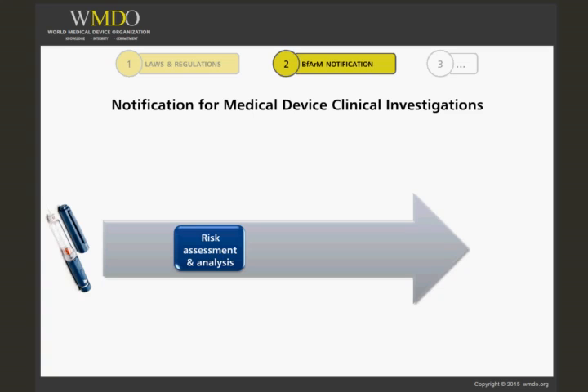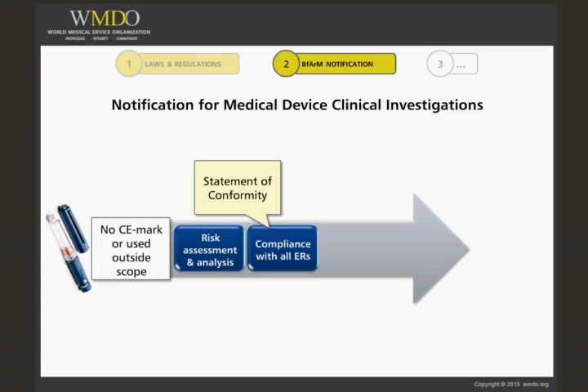Further to be taken into account is that for clinical investigations with non-CE marked devices or devices used outside CE mark scope, the manufacturer must ensure the device complies with all essential requirements as outlined in the Annex 1 of the applicable Medical Device Directive. A statement of conformity must be issued by the manufacturer or sponsor that confirms that the device complies with all essential requirements, except those still to be proven by the clinical investigation, and that with regards to those requirements, all measures have been taken to protect the safety of the patients and users of the device from risks associated with the requirements still to be studied in the clinical investigation. This statement must be joined with the submission file.